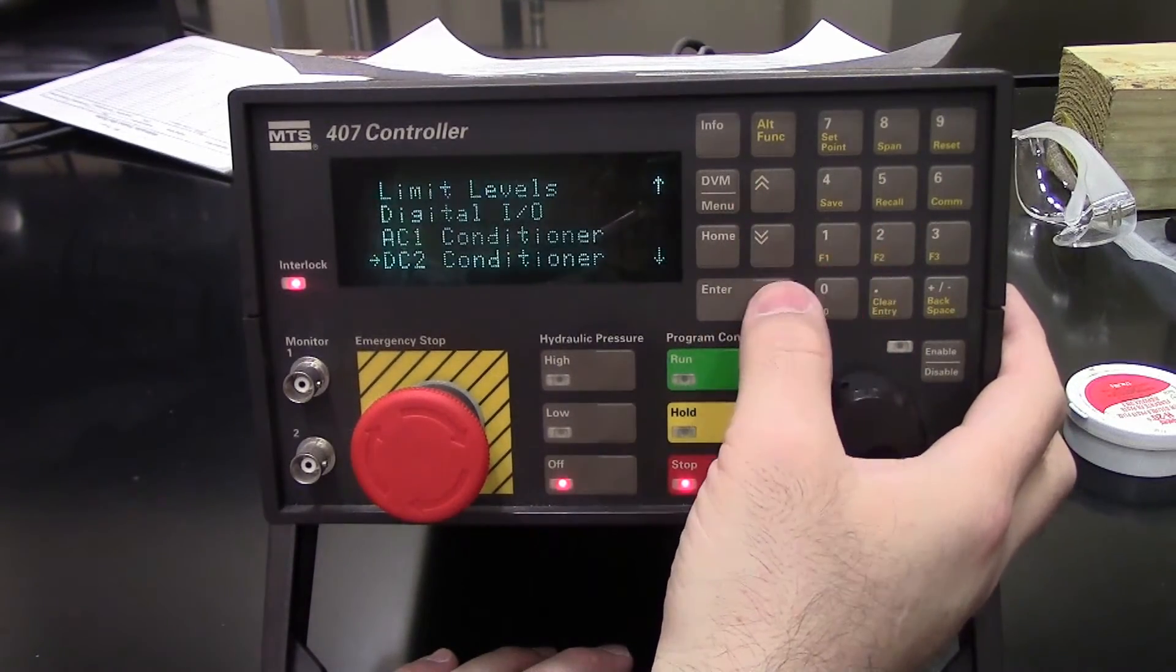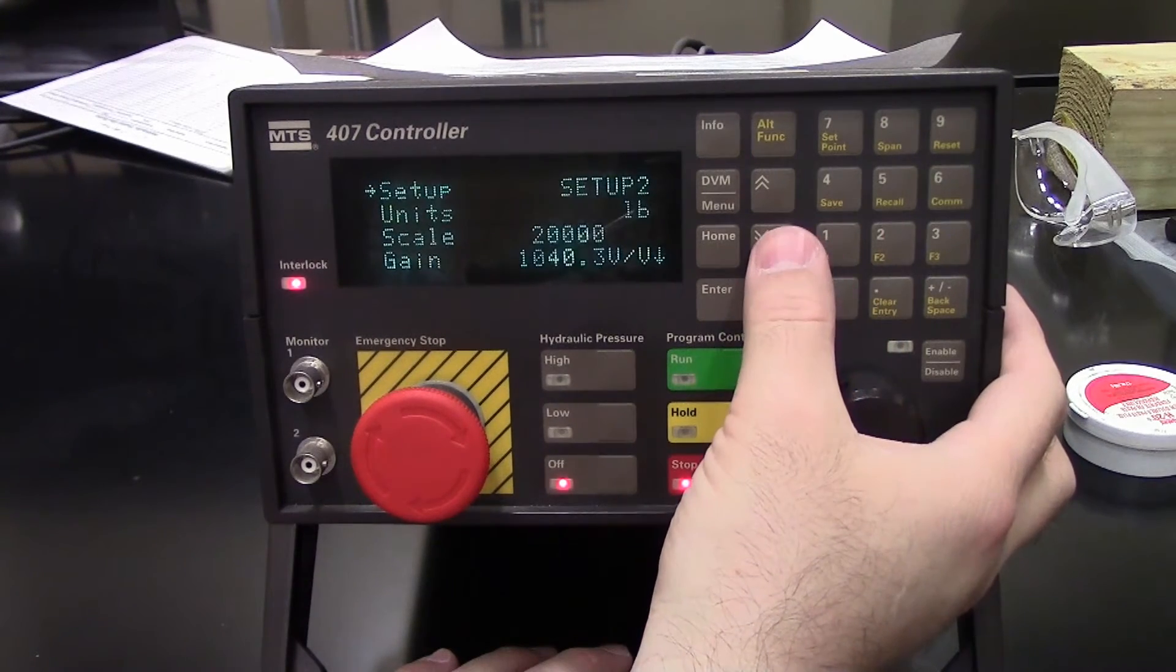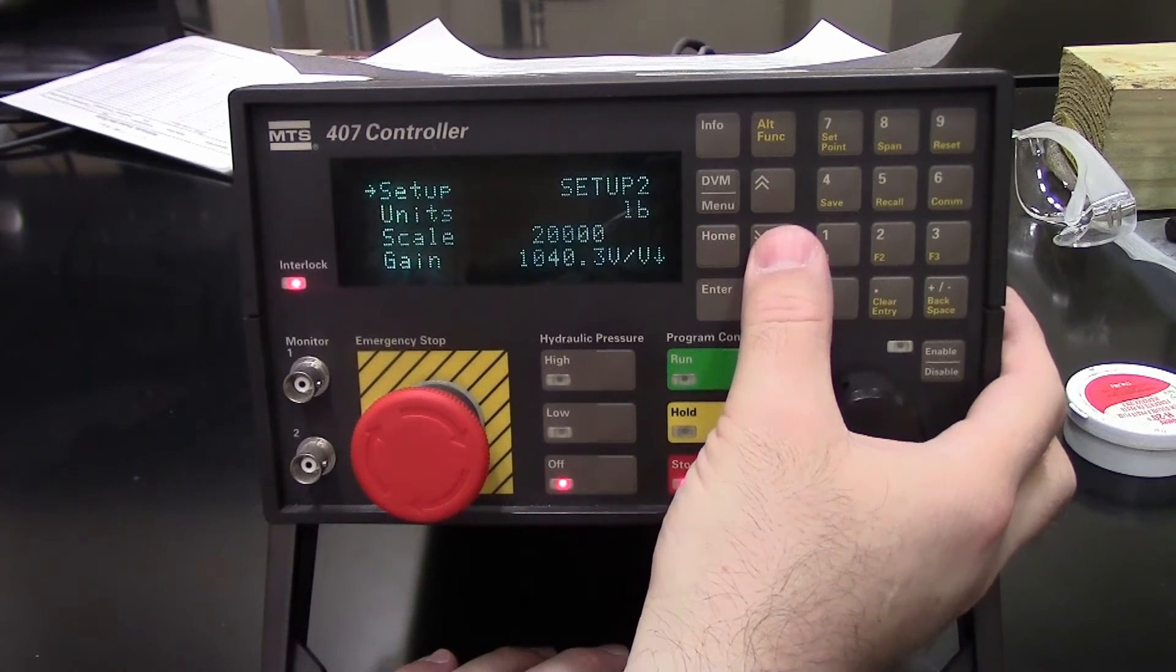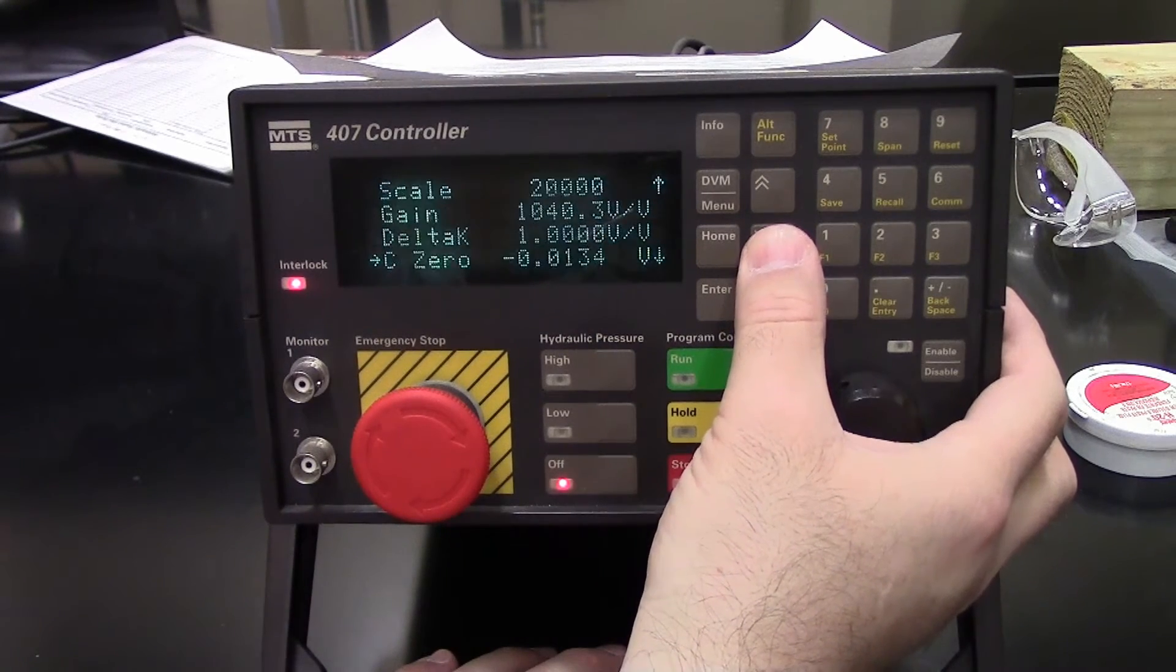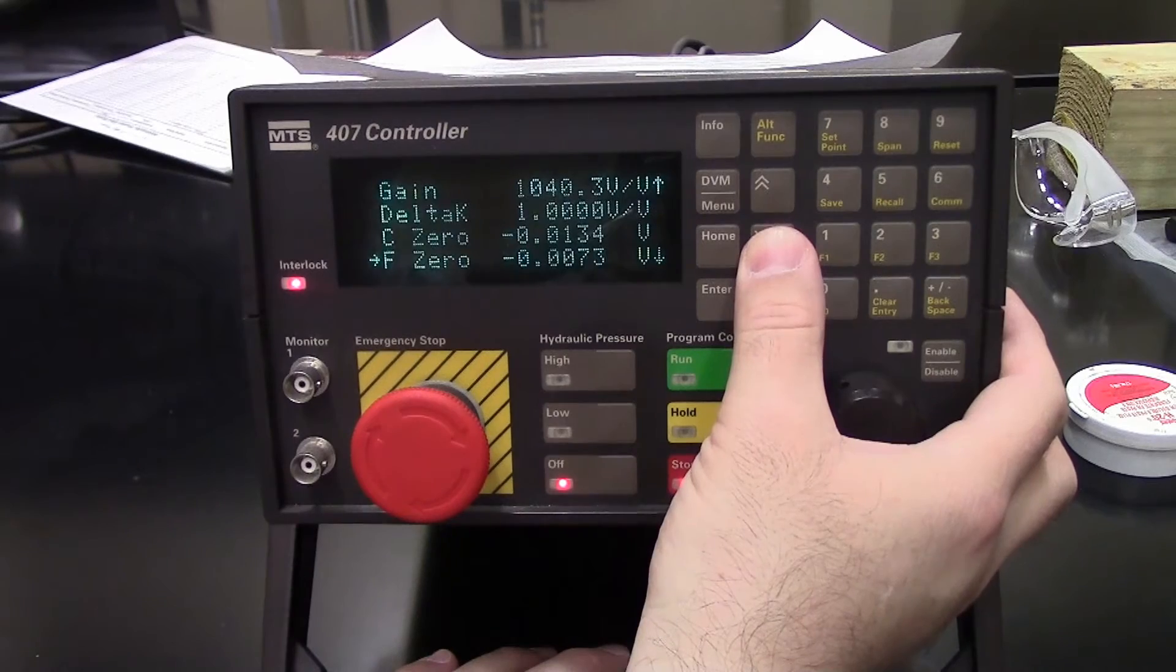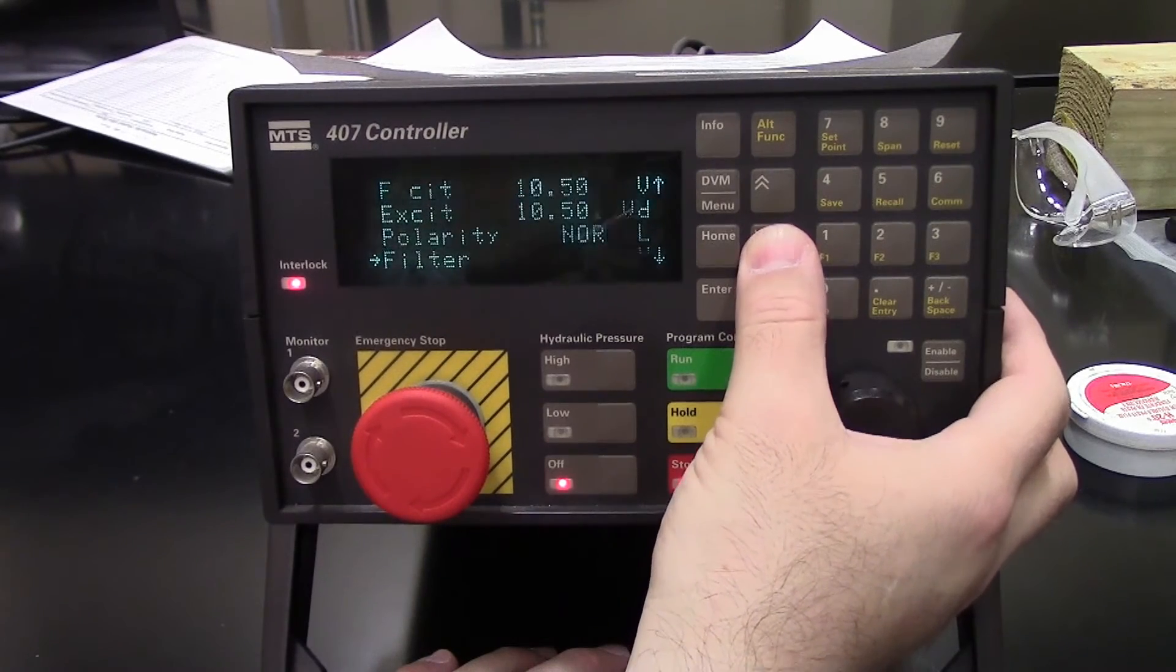Likewise, for the DC2 conditioner - again that's a load cell. This is for setup 2. It's a 20,000 pound capacity full scale for setup 2. It's a 50 kip machine, 50,000 pounds. There's my excitation polarity.